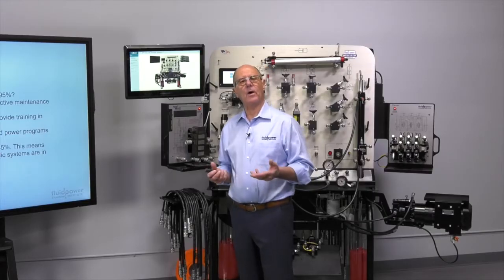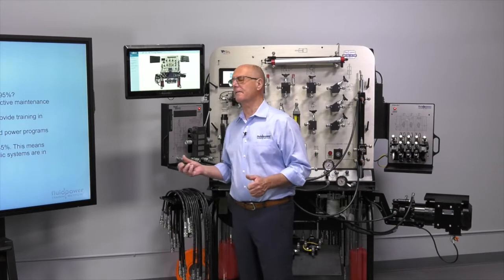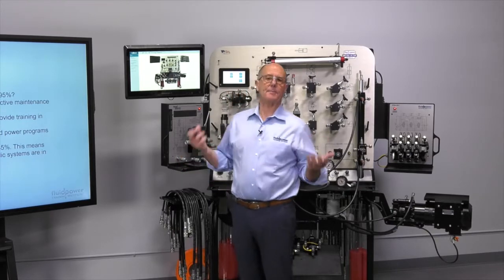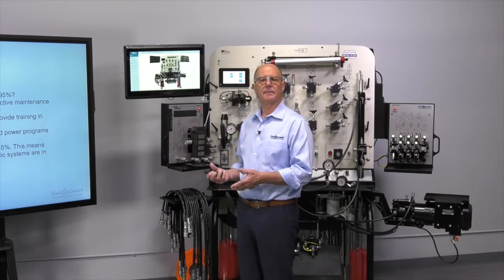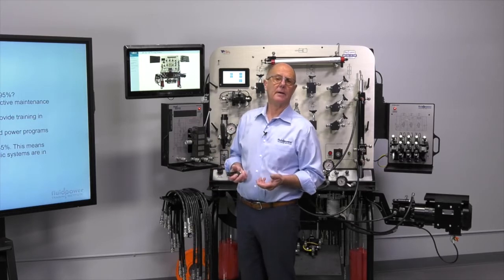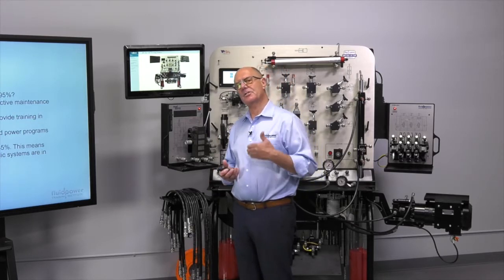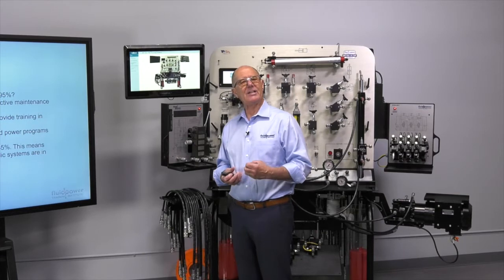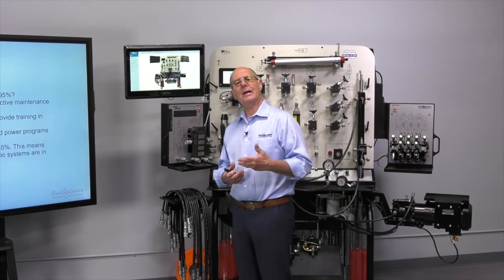Let's go the other way. What if I put so much flow into the valve that I could make up the leakage even when the valve was bad? Then I'm back to square one. So the volume that is displaced during microleak testing is critical to a good outcome.